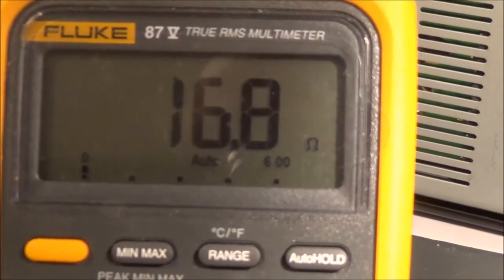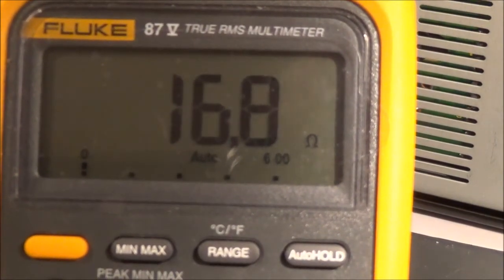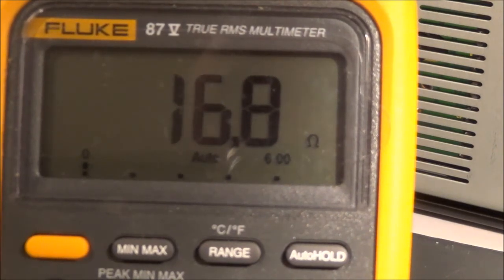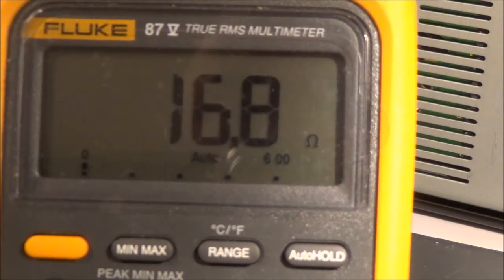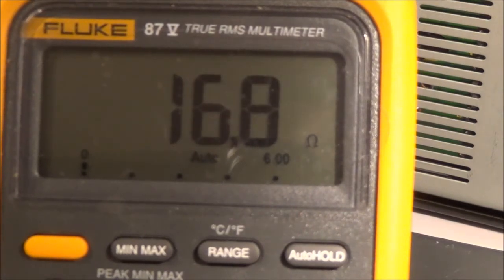Now here's the 2 wires coming directly from the motor, and I've got the ohm meter hooked up. You can see what I'm reading here, which is 16.8 or about 17 ohms. For these motors, you're always going to have a really low reading. If you read it a lot higher, or it's open, then you know you have a different problem.